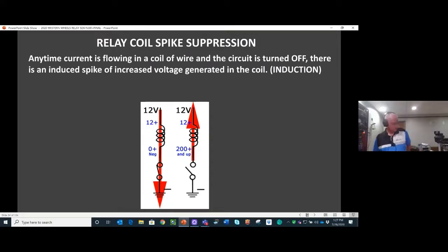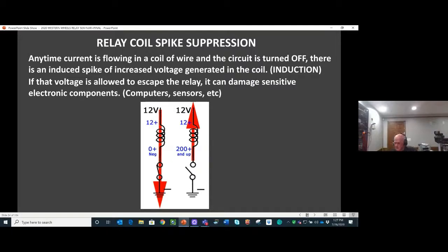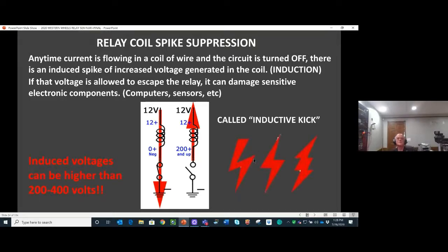Anytime you have current flowing in a coil and then you stop that current, you induce a voltage greater than the supply voltage, and that is called induction. That's how an ignition coil works, by the way, a step-up transformer. If we allowed that voltage to escape into the circuit, we could damage computers or sensitive electronic components. So we've got to control that spike and keep it in the relay. It's called the inductive kick, and it can be 200 to 400 volts.